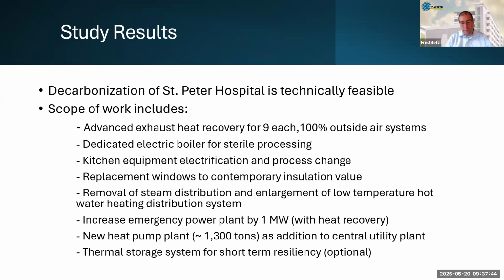There are the first few products now on the market of steam generating heat pumps. They're not ready, what I would call, for this task yet, because most of them make 2 and 3 psi steam. For sterile processing, you really want something around 40 to 80 psi steam. But to me, that means that in this timeline, 10 to 15 years is a long time in the realm of product development. 10 years ago, we couldn't have even done most of this work because the technology didn't exist. So another 10 years from now, it's plausible that there's something better than an electric steam boiler. Similar with the kitchen equipment electrification. It's actually a heat pump conveyor dishwasher that's being used here.